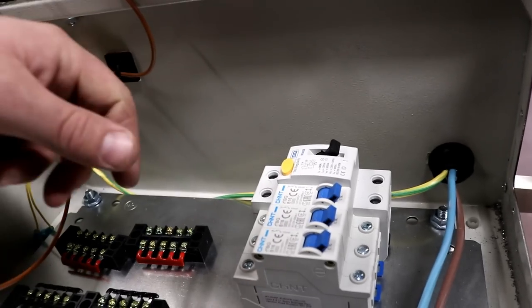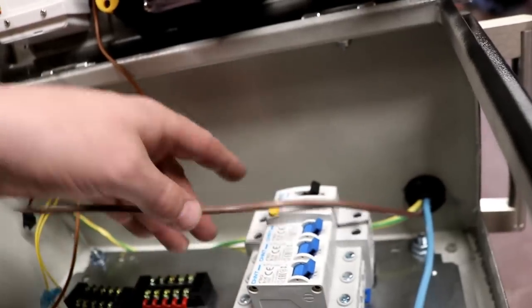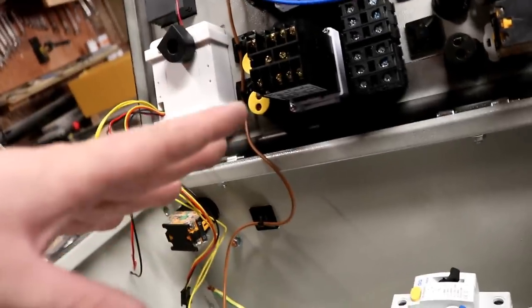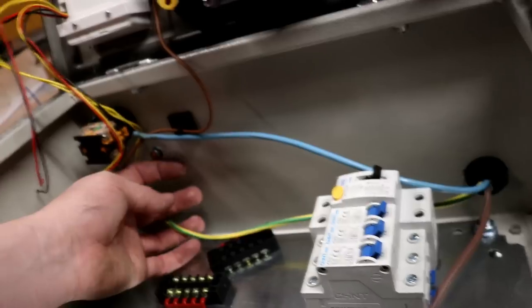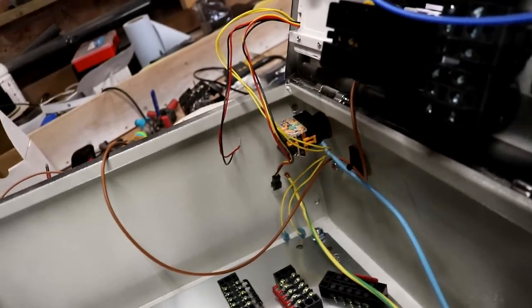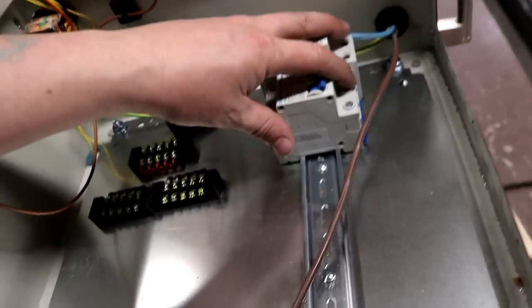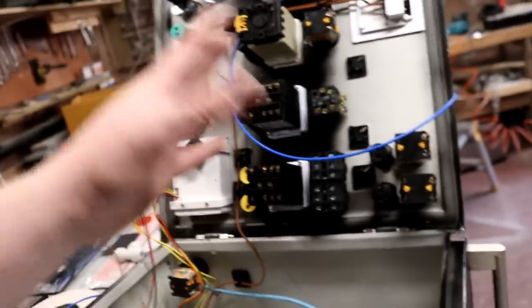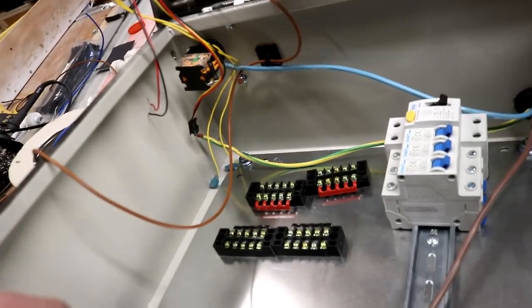If there's no power to the solid state relays the circuit will remain open. If there's a fault on the solid state relays they will trip the RCD if they fault to ground. If they don't fault to ground and they fail short circuit, we'll have a current surge and that will trip the MCB, so we should be protected in all areas. The neutral will go through the MCB and the earth will be connected onto the earth bar on the box. That's early doors yet but the main circuit inputs and outputs are in.